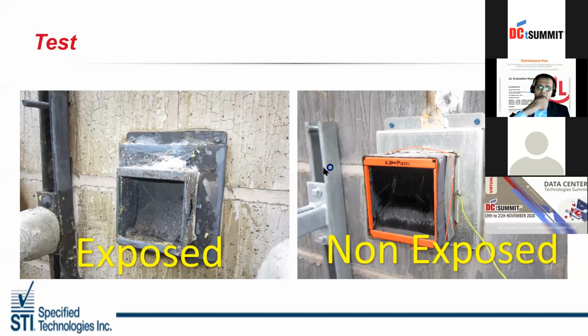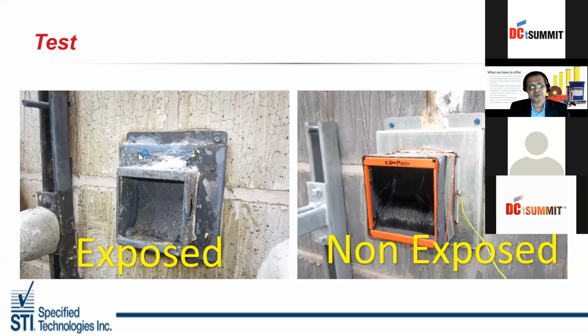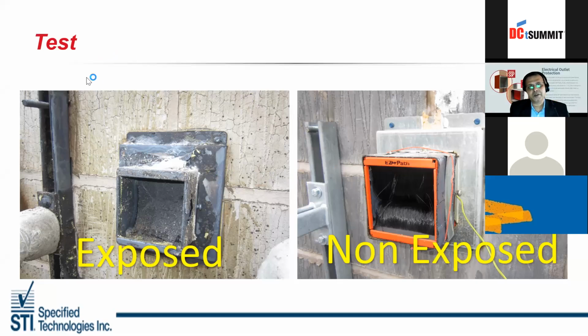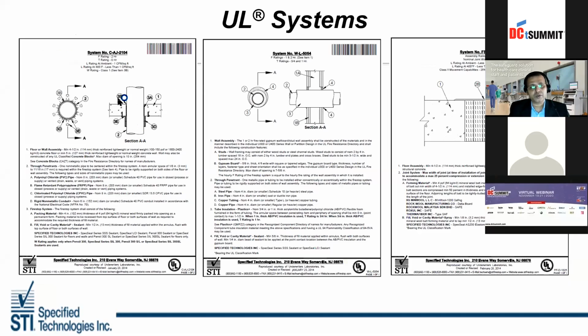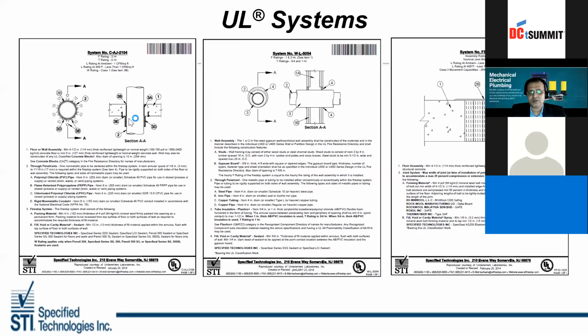So how is a UL tested system defined? There are 3 different scenarios where I have tried to explain a UL tested system. This is the first one. Towards your left-hand side is a combustible pipe passing through a concrete wall or a floor. The second one is a fire rated gypsum board with an insulated pipe. And the third one is joints. So all these scenarios show how a UL tested system works, and you can also go directly to UL and check this part.